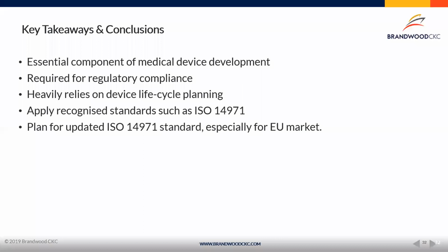One, I think taking the application guidance out of it and putting it into the 24971 document is good. I think that helps companies understand how to apply that to their device. But two, I think it does clarify not only some definitions, it puts some more emphasis on this risk-benefit profile, and it creates a better plan upfront. So you have a better understanding, and you have a better pathway map for your risk management activities.